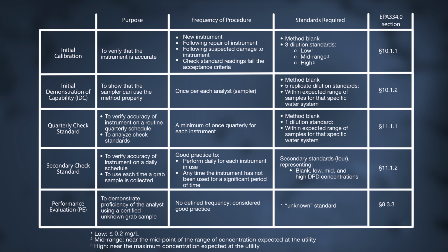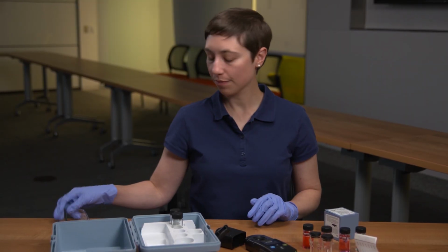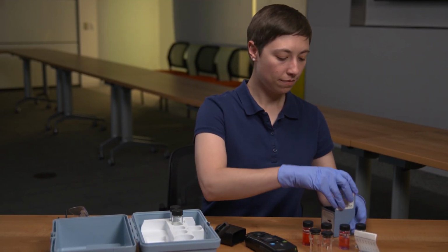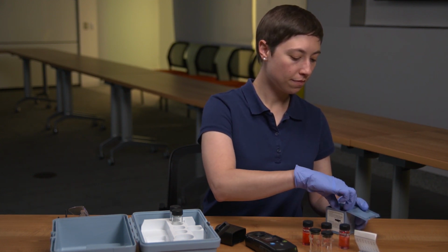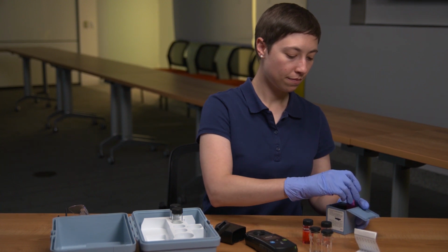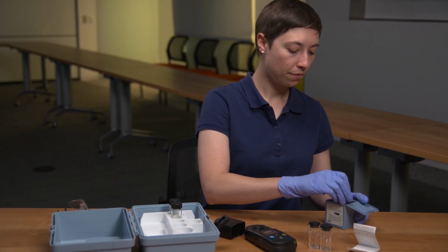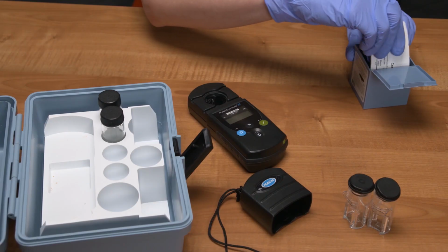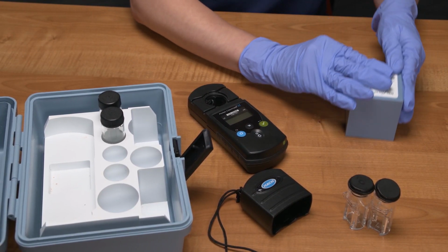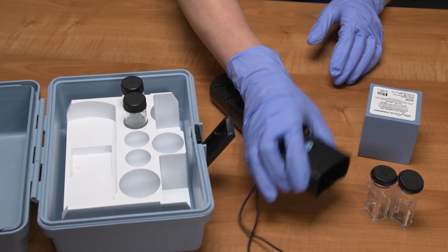This video demonstrated the procedures for performing calibration verification checks for a chlorine meter using primary and secondary standards for chlorine grab samples. This table summarizes the procedures and standards required for performing calibration verification checks for a chlorine meter. Remember, validating the factory calibration curve and performing the initial demonstration of capability, or IDC, are one-time startup procedures. The routine calibration check must be completed at least quarterly. Every sampler or analyst needs to demonstrate their ability to perform the analysis consistently, to ensure instruments are operating properly and to ensure that reagents used are effective.